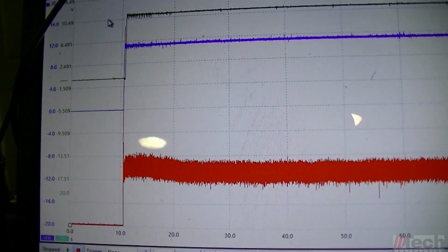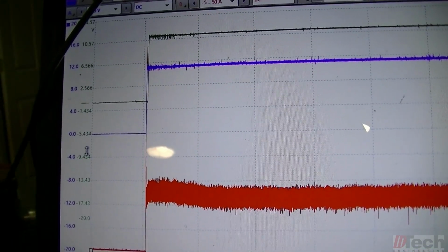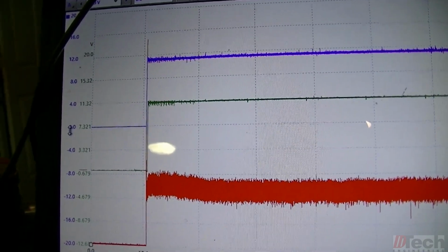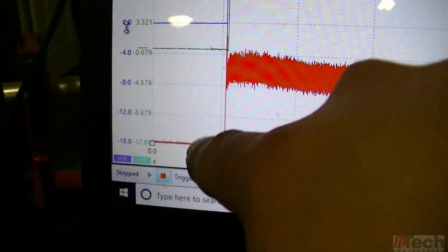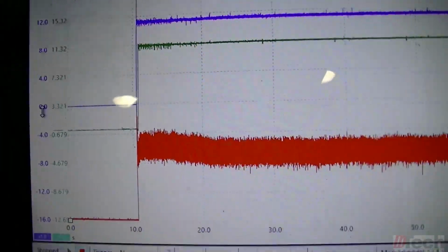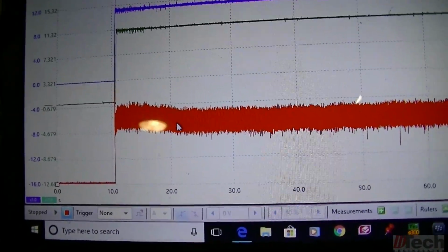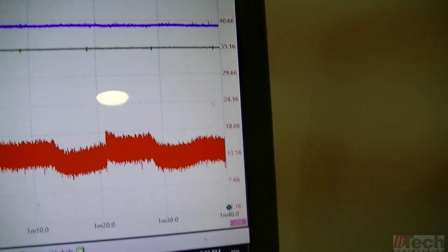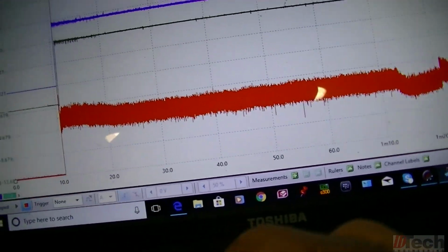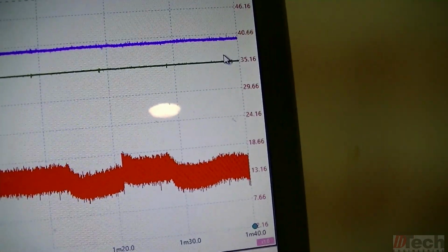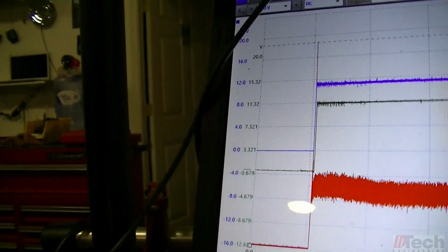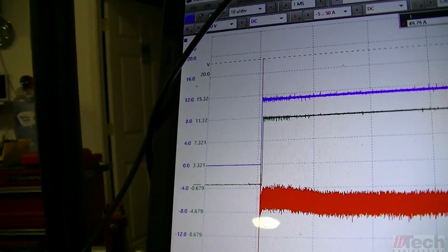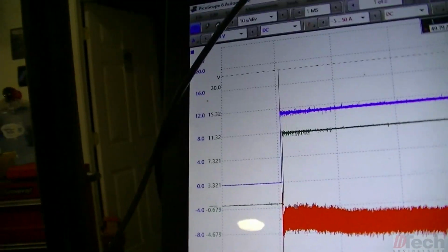On this, if you can see how the red spikes up as soon as it kicks on, and then drops down and starts doing the pump motor cycling. And you can tell over here, amperage drops down a little, goes back up, then drops down. The running amperage is below 18. So there's where we're seeing the spike in the amperage on the initial turn on of the electric motor, actually rushing in.